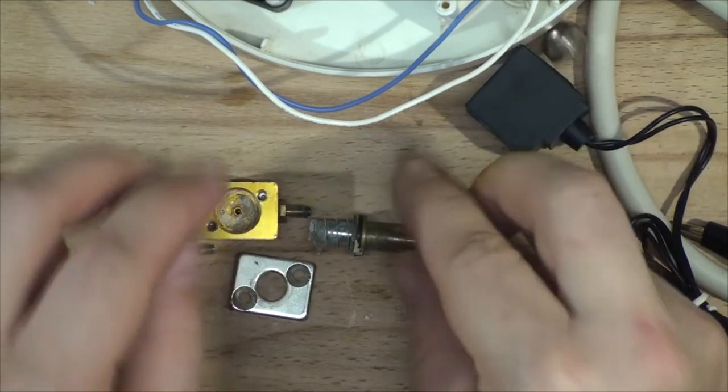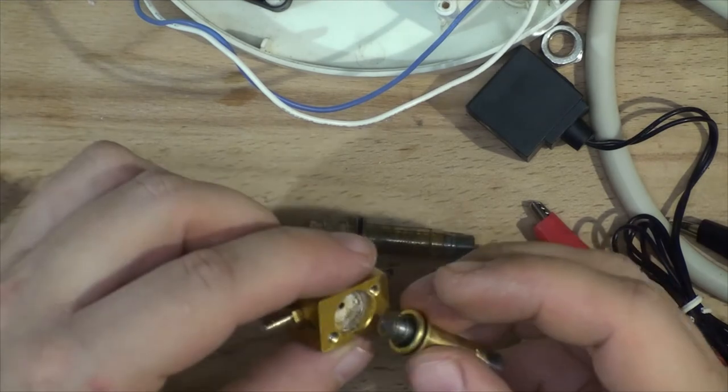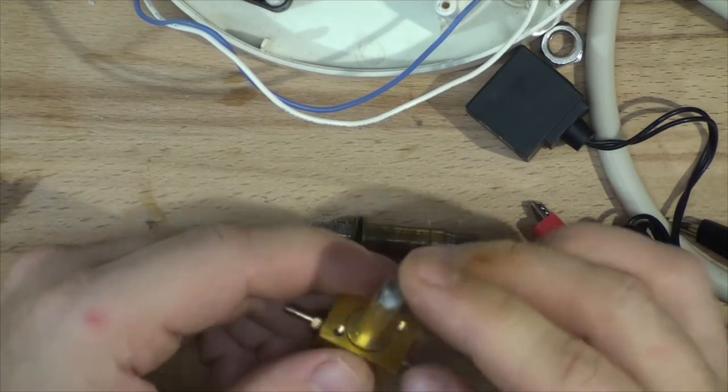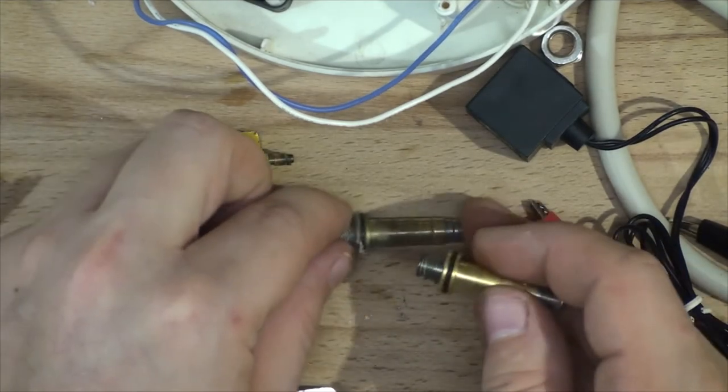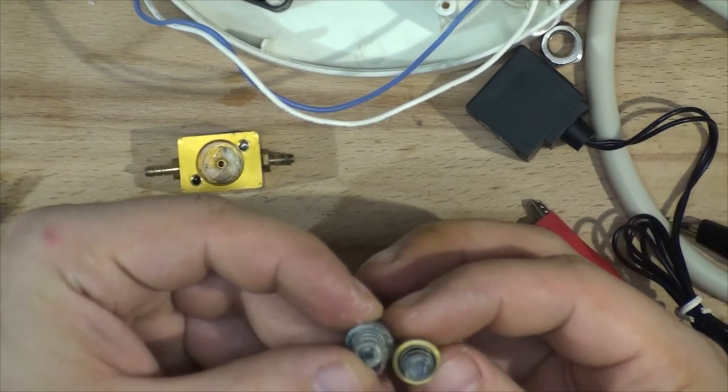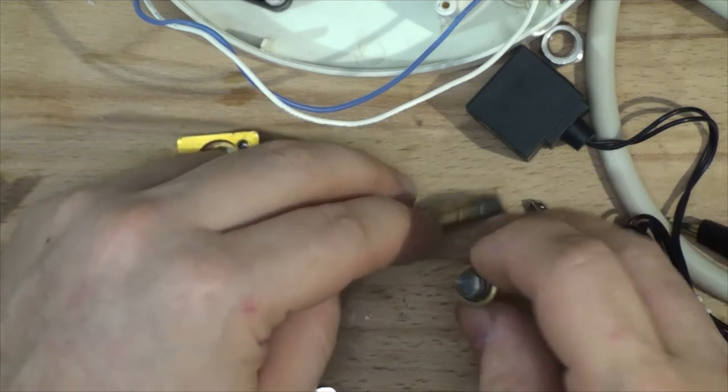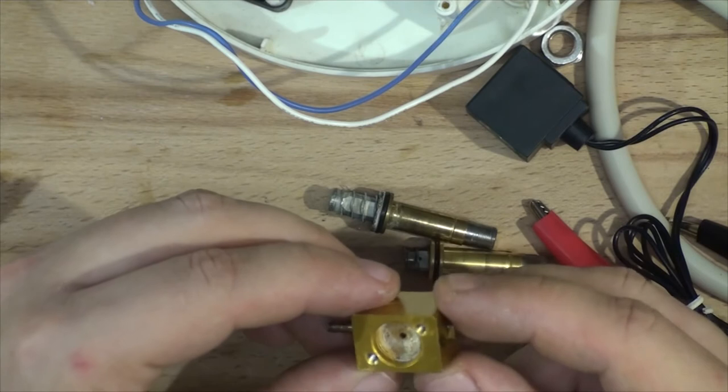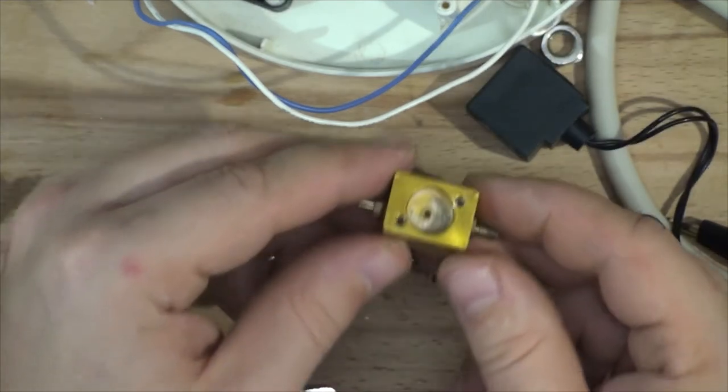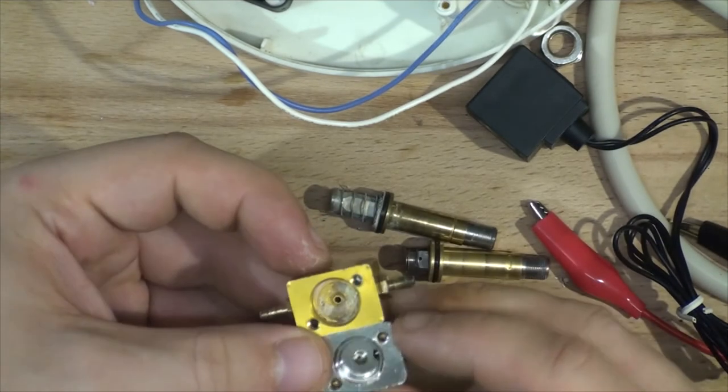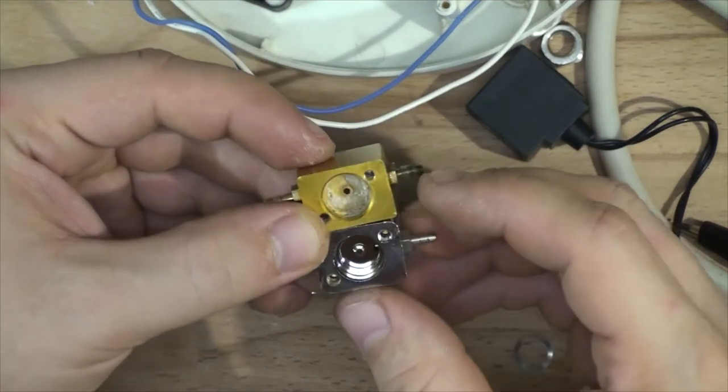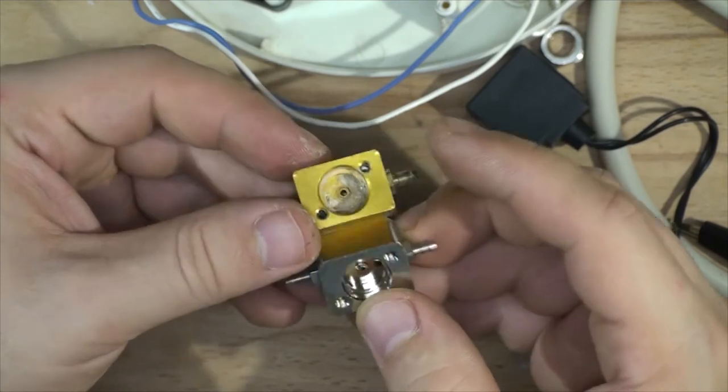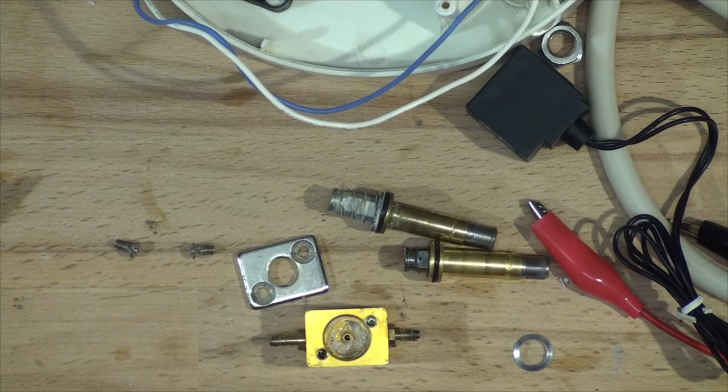Let's pull apart the good solenoid. Obviously the coil we won't be using. It looks like it's just a direct swap. They look identical - same size, same valve, same everything. So what I will be doing, I will be cleaning this body. It's definitely clogged up with all sorts of stuff. That's a new body. The diameter of the hole is definitely larger in the older one, so that's why we will be using the old body.